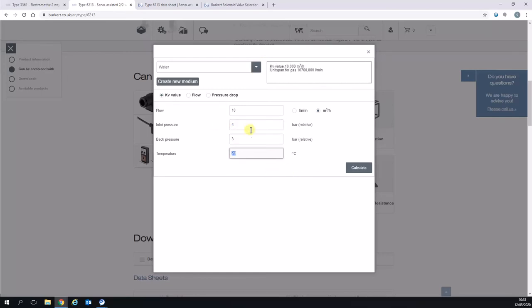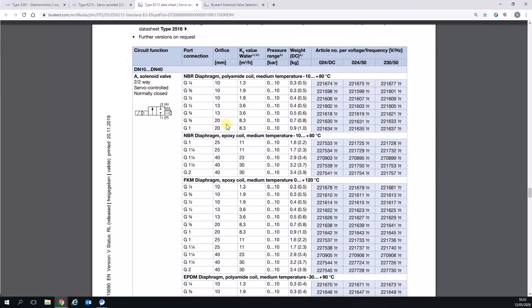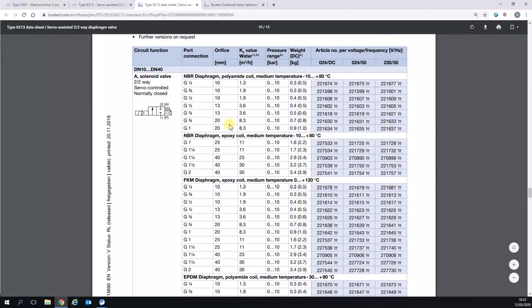We can use this KV value now to find the right type of solenoid valve. If we go to our data sheet, we need to achieve a KV of 10 at least. You can see here on screen that a G1 or one and a quarter with a KV of 11 would be suitable for this particular application.